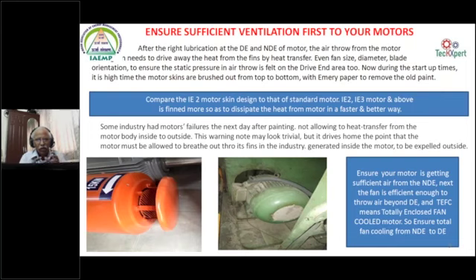That is why you can see the IE2 motor and IE3 motor, you will find the IE3 motor is finned more. You can see the fins at the back of the motor, the actual fins. Fins are more. You see the green color motor, the fins are less. The motor has to dissipate more heat, then only it can run better as such.